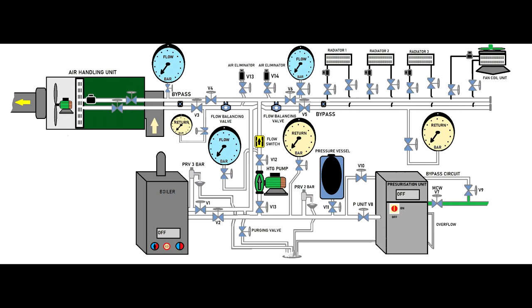Before putting water into the installation, I always check the pressure onto the pressurization vessel, and if the pressure is wrong I'm pressurizing the system myself. I just want to make sure that I will provide for the system the right elasticity to have the smallest possible variation in pressure when the heat increases and decreases as per building demand.